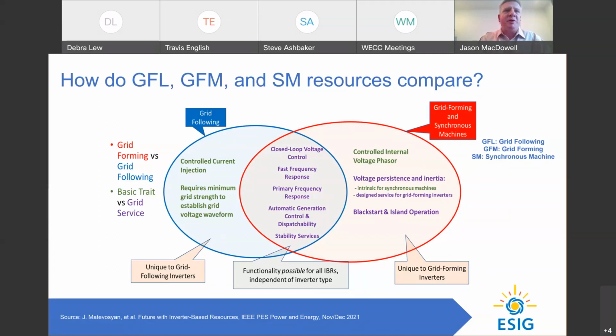But closed loop voltage control, fast frequency response, primary response, balancing, and stability services are certainly all possible from all IBRs, whether grid forming or grid following. But grid following controls, again, primarily use a controlled current injection and require a minimum grid strength to be stable, as opposed to grid forming and synchronous machines, which have voltage persistence and inertia to support grid stability during disturbances. They also have the capability of black start and island operation. Next slide, please.